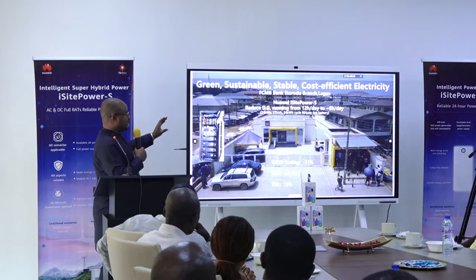For this particular solution, we are seeing a reduction in terms of diesel generator running time. Most of the time, banks have grid power and maybe two generators as redundancy. If you're using this solution, one generator can be switched off, and the second generator runs for a shorter period, so you have better savings.